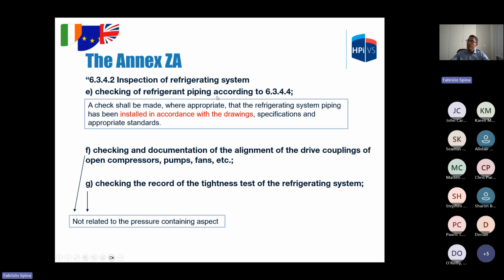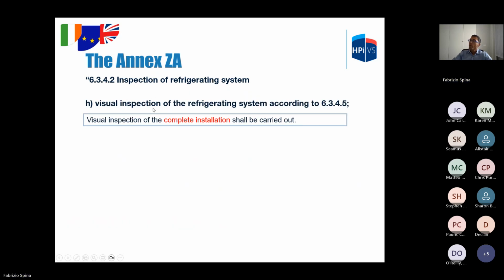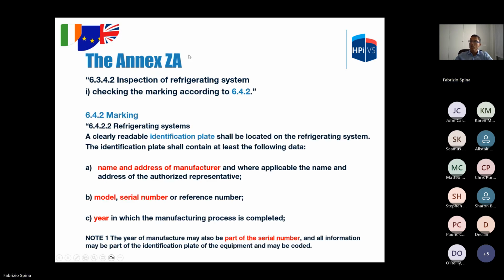Checking the refrigerant piping, that means installed in accordance with the drawing. Checking the documentation on the alignments of the drive couplings of rotating parts. Checking the record of the tightness test. These two points are not really related to the pressure containing aspect, so we are not really checking this during our inspection. Visual inspection of the refrigeration systems. That means an inspection of the complete installation. And as last point, checking the marking according to the point 6.4.2.